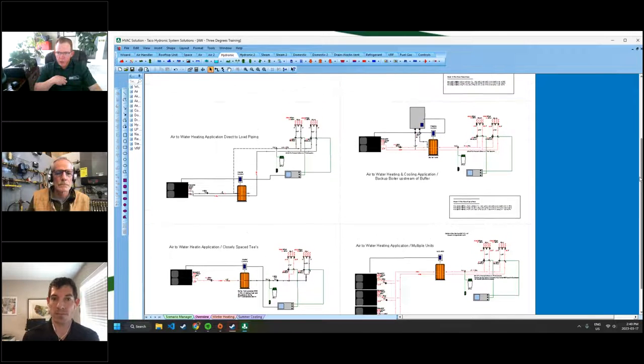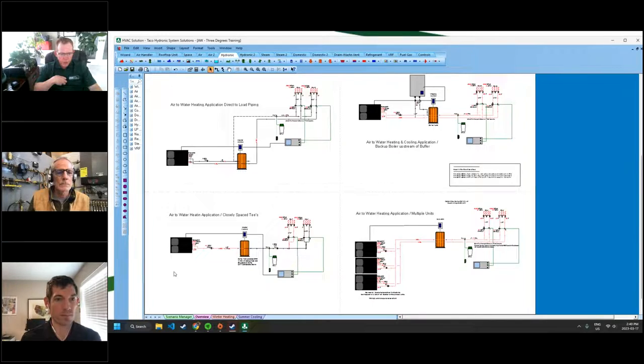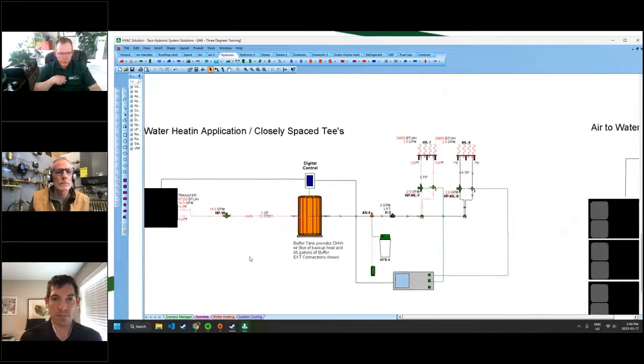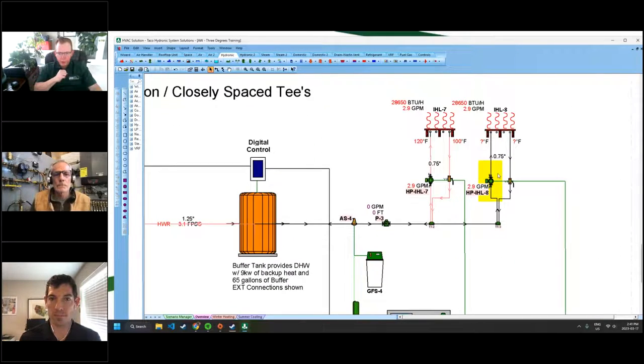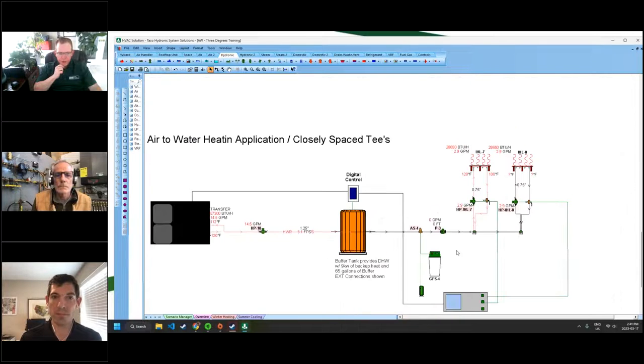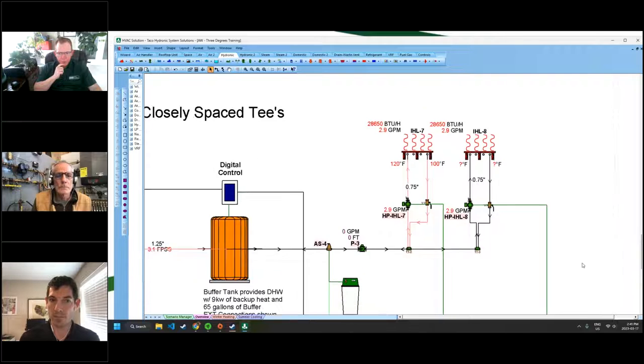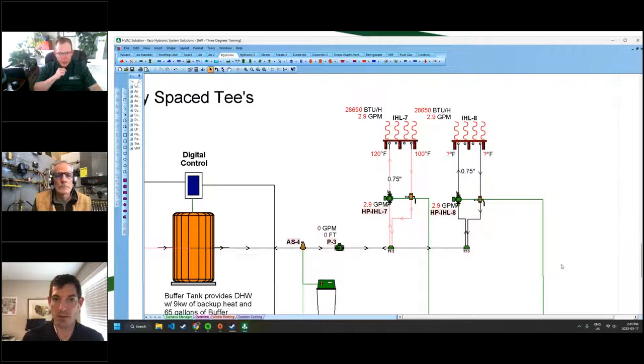We did the direct to load. We've done that one. I want to talk about this one. This drawing, I'm actually missing the return pipe, so I apologize for that. This is exactly the same. So we have an air-to-water heat pump feeding a buffer tank. And what's different here that I want to touch on, that's not a good idea, is closely spaced tees. So what's happening here is we're coming off this storage tank, feeding into the first one at 120 degrees. We are coming out at 100 degrees, going into the second one doing the exact same thing.